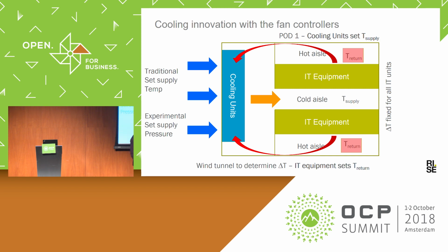Then what we want to do is specify a return temperature. Now, to specify a return temperature, we are actually saying we want a delta T across all the hardware of X, so we want to dial in a delta T across the hardware. Most people work on set points of temperature or pressure. In this case, we're going to try to specify a delta T across the IT, irrespective of what the workload of the IT is, because as the IT does more work, it will get hotter, and therefore its flow rate will increase—but the delta T may not be the delta T we're asking for.